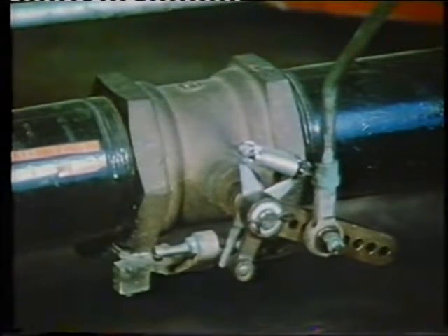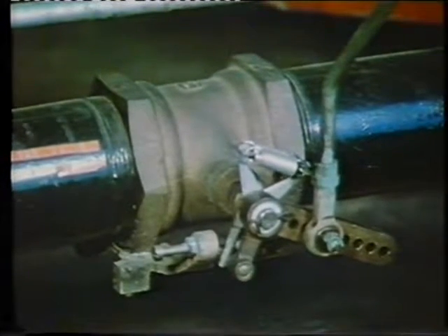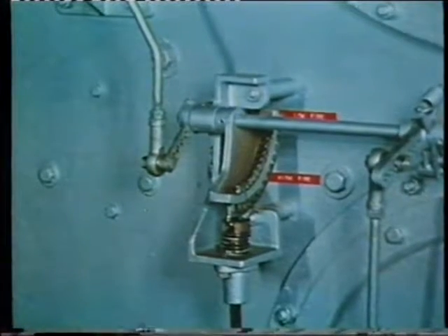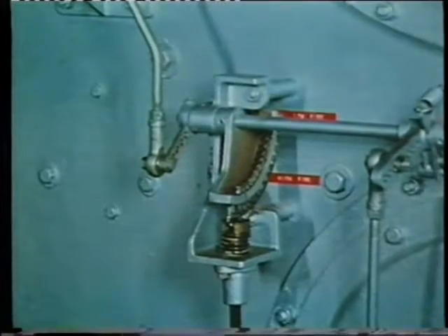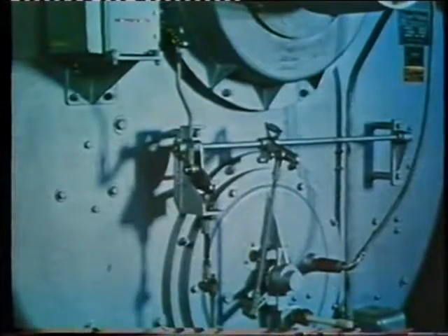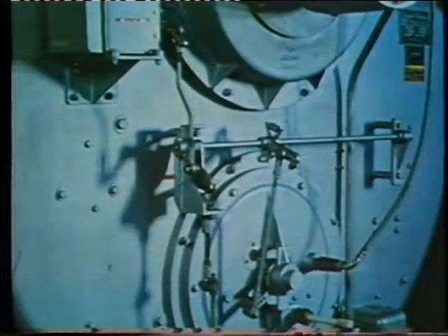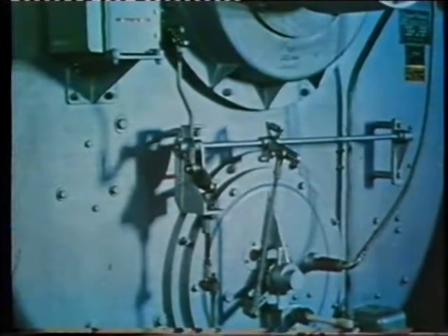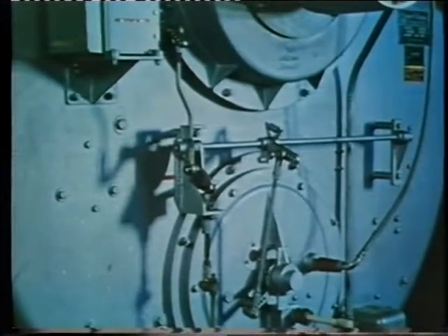Gas flows through the motorized valve to the modulating butterfly valve, which controls the flow of gas from low fire to high fire settings. The position of the butterfly valve disc is governed by the gas modulating cam. The butterfly valve and the combustion air damper are controlled simultaneously by the modulating motor, which varies combustion air and gas for changes in boiler load demand.